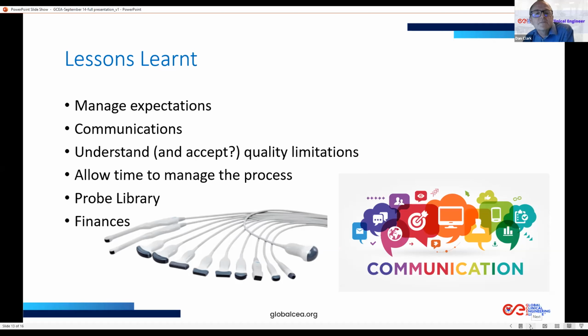But don't underestimate the length of time it takes to actually manage that whole service and keep the whole thing working as a single process. One of the key frustrations that we've had in the past is the availability of probes. If a probe breaks or we need to bring in a new probe, it will need to go through image quality control before we can issue it to clinical service. And this takes time. But the clinical teams are often really, really busy and they haven't got that time to wait. So that leads to frustrations.